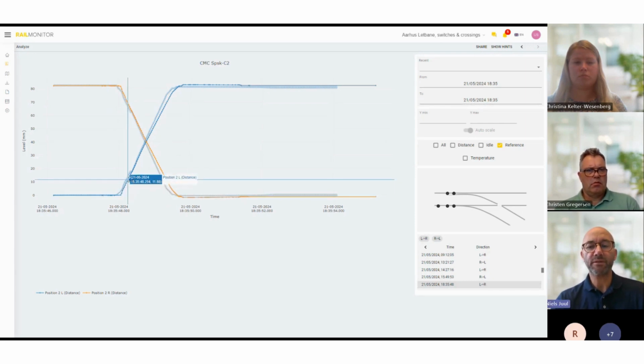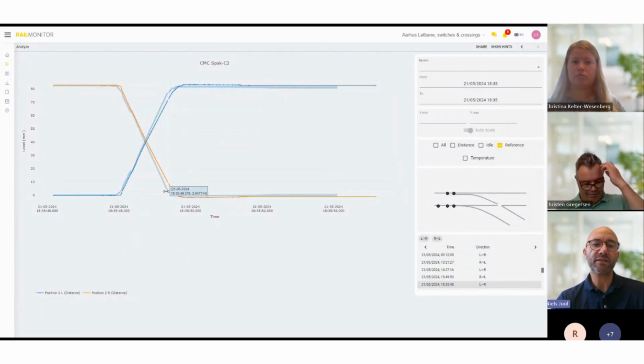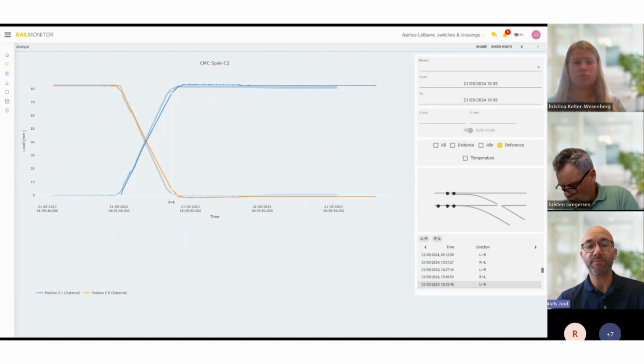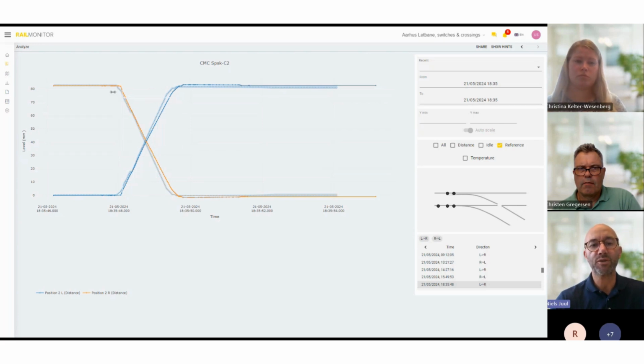The reason for the yellow marking that you saw before is because the movement is outside the limit of the baseline. The baseline is the dotted line you see here, and also the light blue. So here it actually uses the system to see if there is anything wrong. In this case, nothing especially is wrong. The behavior is more or less as it should be.